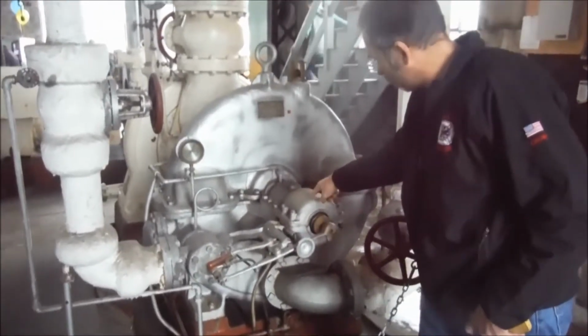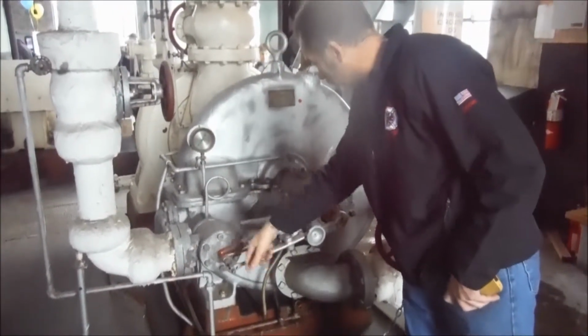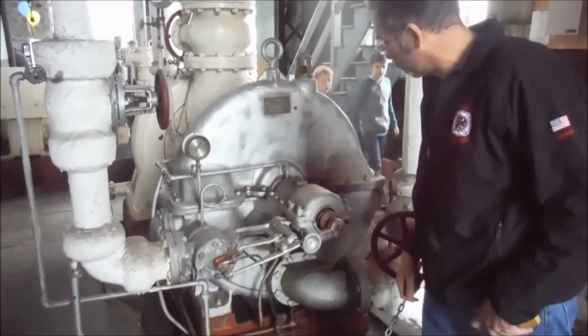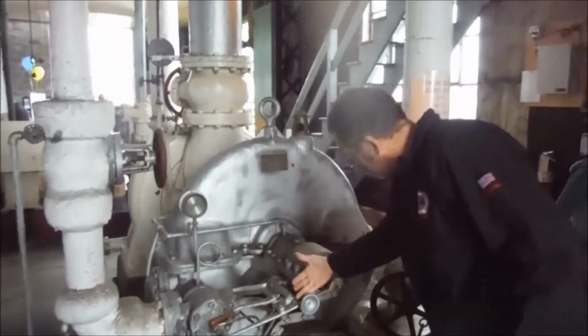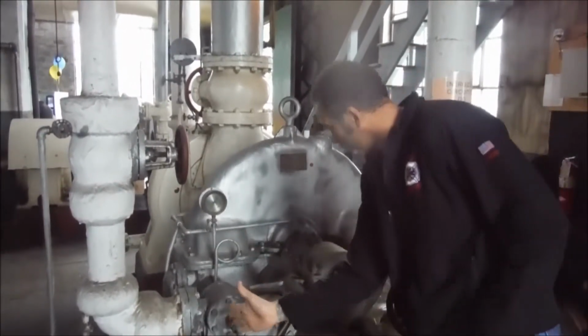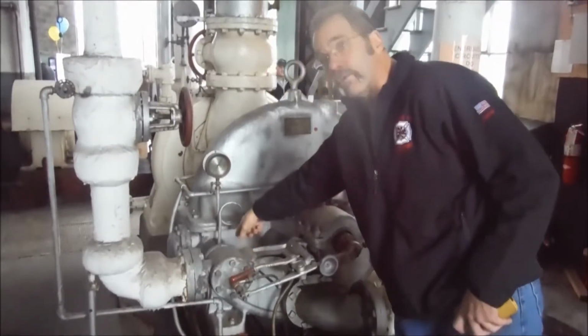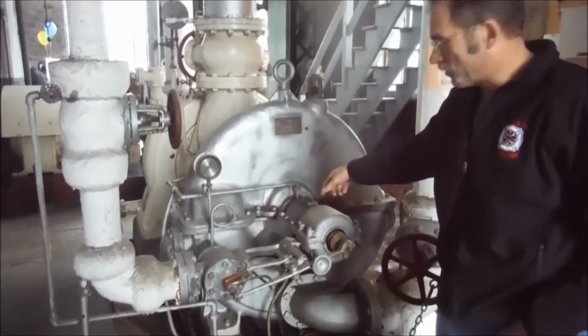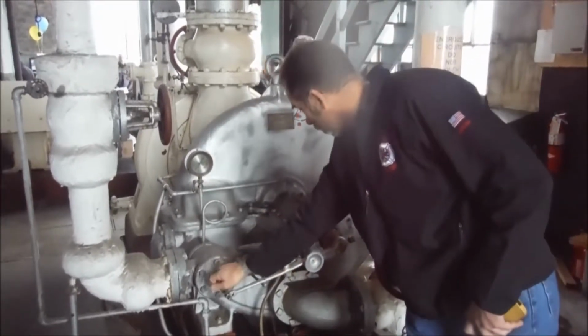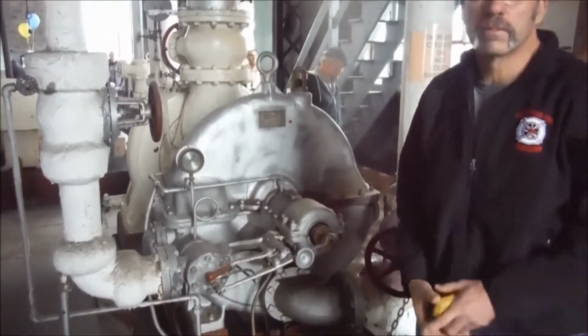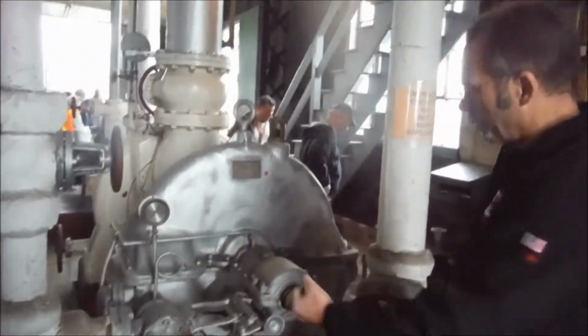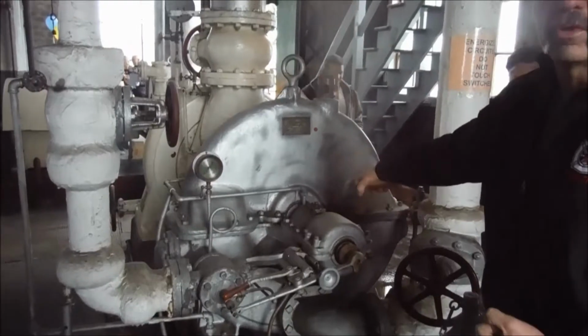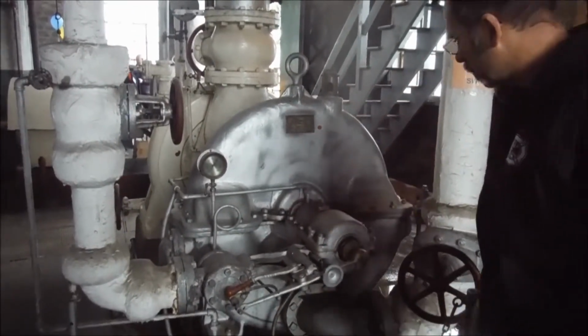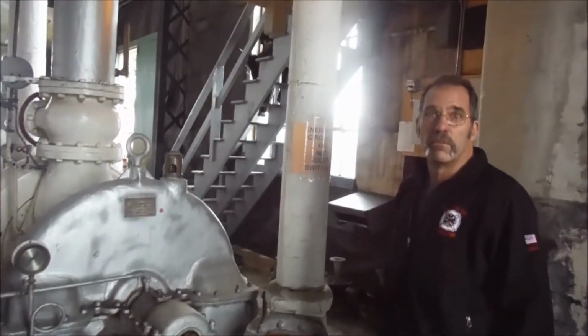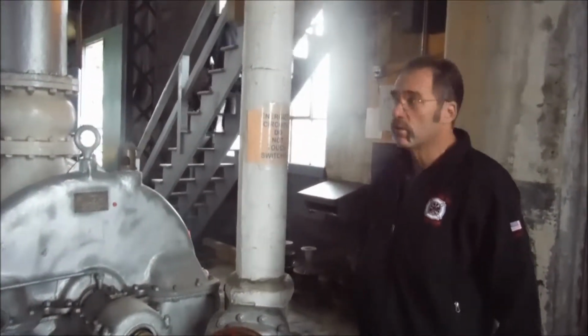This is attached to the shaft, and this will probably be some kind of constant speed governor. So the faster the turbine goes, this would push out against spring pressure, causing a force in there to close down on the steam admission valve. Right, so it operates at a constant speed, and then this is either a manual trip or you pull it to get steam going in to get it started till you get RPMs and get your governor in service. It's not that dissimilar to what was still being used for steam turbines in the 60s, when ships like this were built.